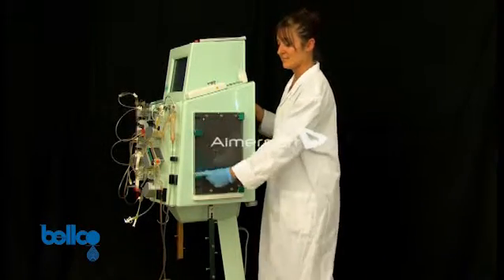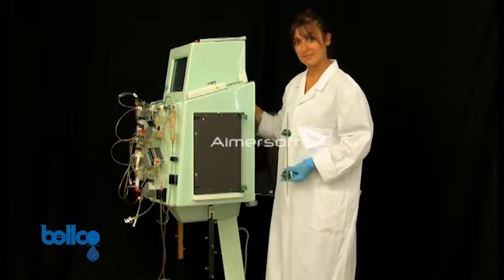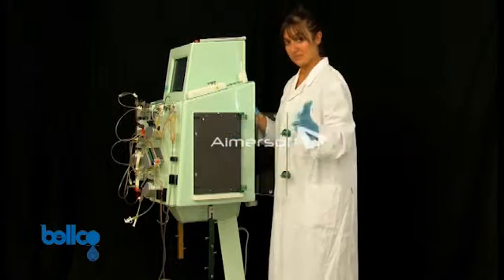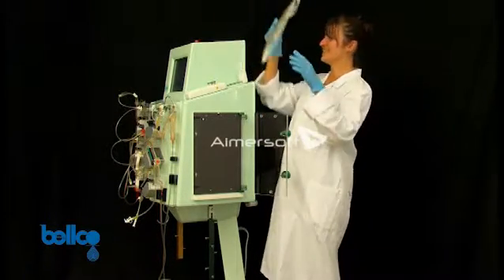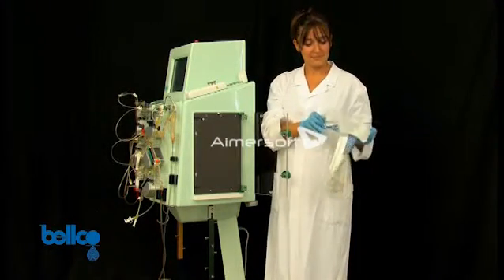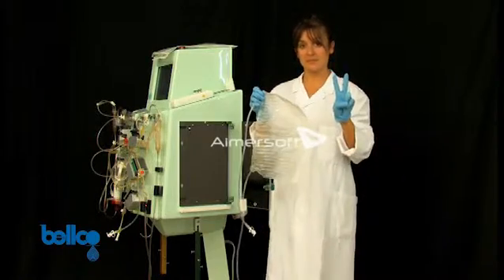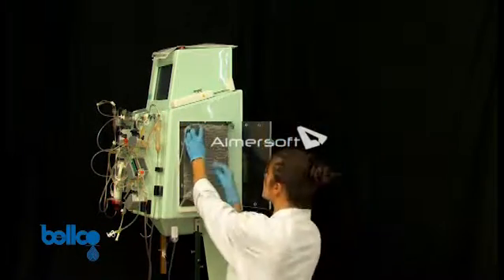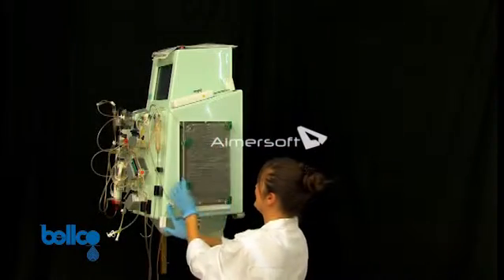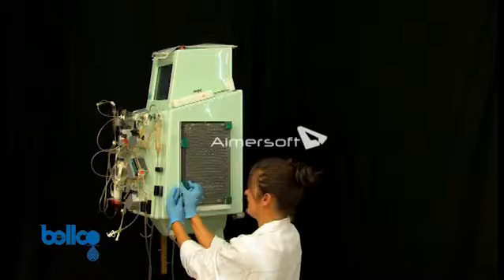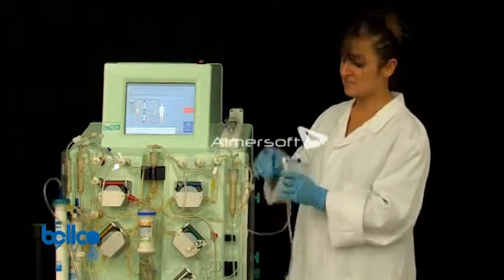Open the heater cover and connect the single-use device to the heater bag. There are 3 holders on the upper part and 2 on the lower part. Take the heater bag, using 3 of the holes in the bag on the upper holders, and on the lower holders using the other 2 holes. After positioning the heater bag, connect the lines to the single-use device.